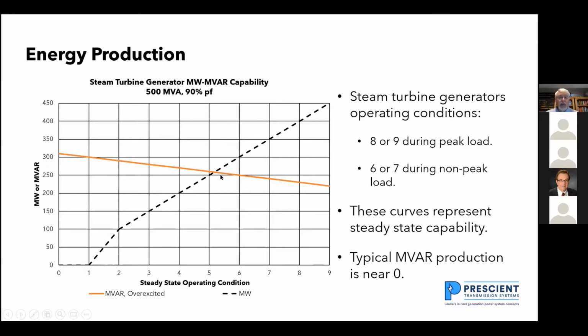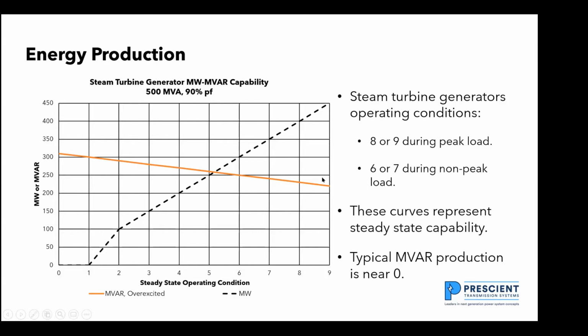On a light load day, I may be operating the same unit down here at condition 5, which would be 250 megawatts. So the amount of power I'm producing by a machine is based on the amount of energy I'm selling. When I look at the MVAR capability, this machine could put out, at condition 9, a little over 200 MVAR. And if I unload the machine, I can push 300 MVAR. These are steady state load values on the machine.